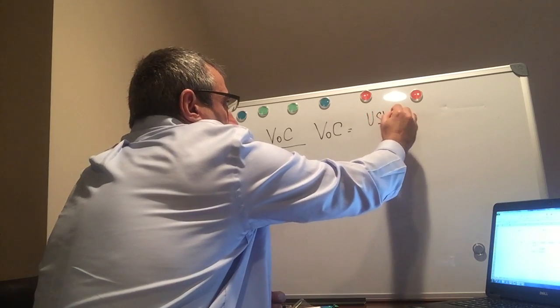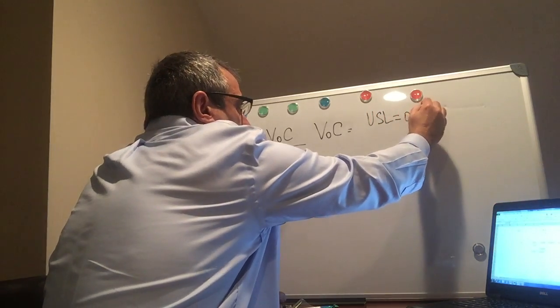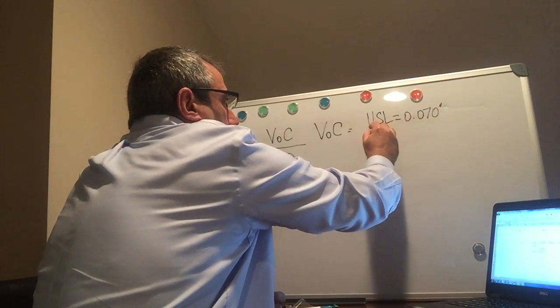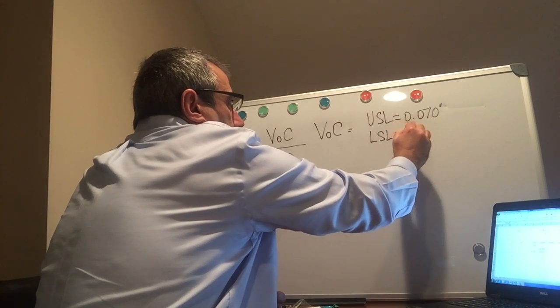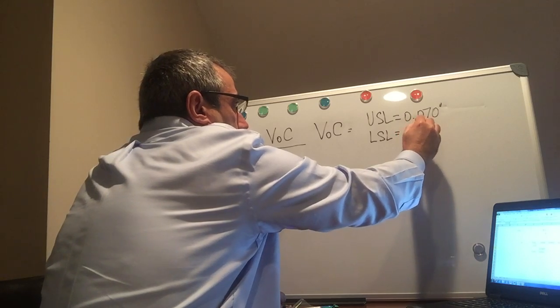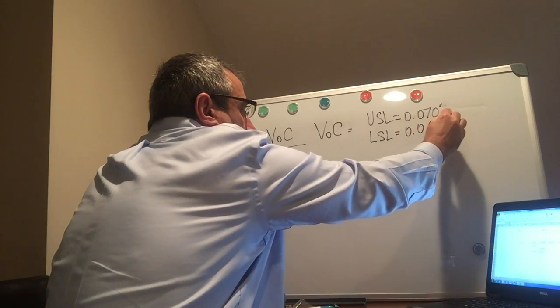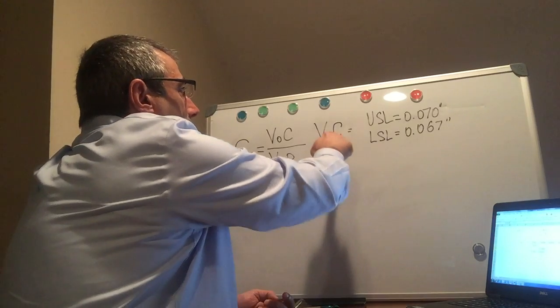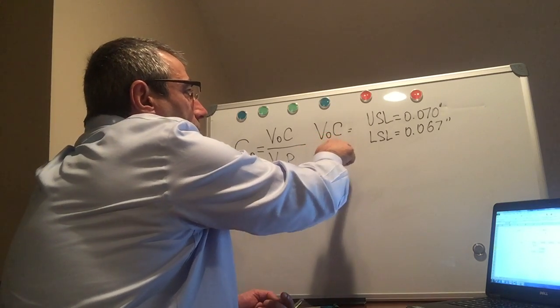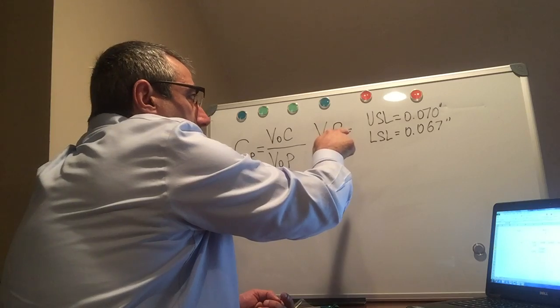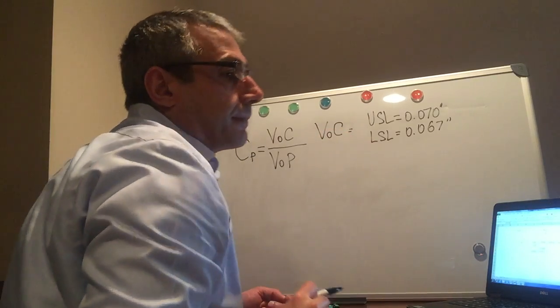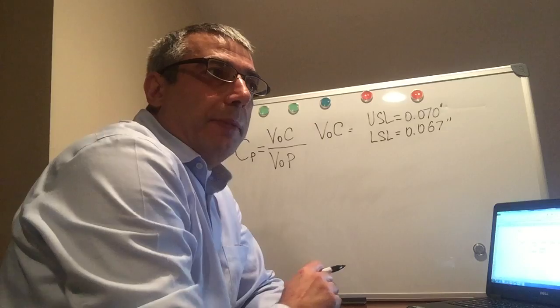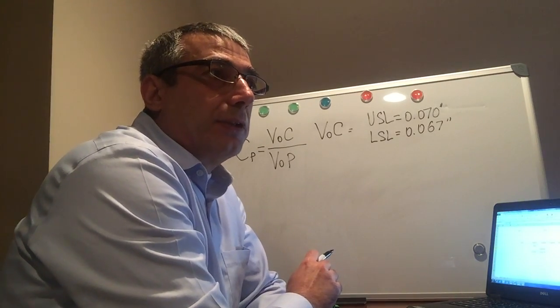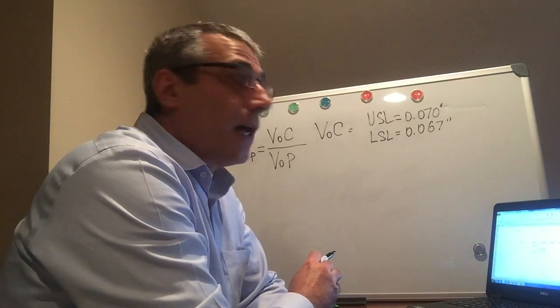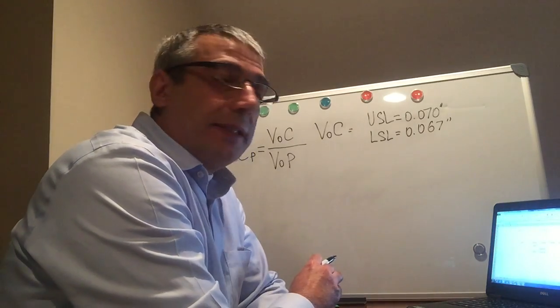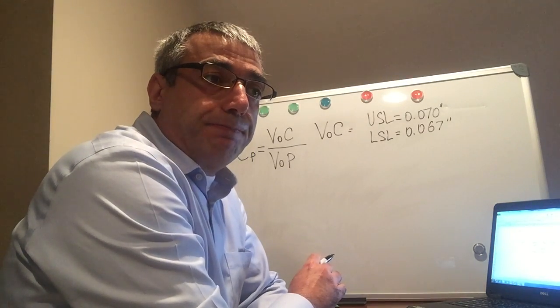Let's imagine the customer wants our catheter to be within an upper specification limit of 70 thousandths of an inch and a lower specification limit of 67 thousandths of an inch. So in this situation, voice of the customer implies that the outer diameter of the catheter shall not be more than 70 thousandths of an inch and shall not be less than 67 thousandths of an inch.